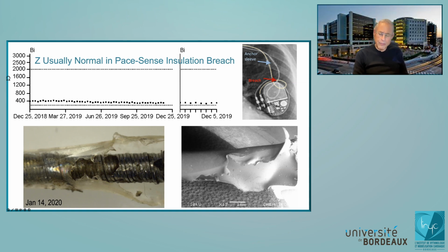So the question now comes, how close does the contact of the lead need to be with the can to measure an abnormal impedance? And how close does it need to be to get an abnormal electrical signal from where you're picking up, say, signals off the pectoral muscle that will enter the pace-sense circuit through that insulation breach, because that's sitting right on the pectoral muscle. So here's what you need to know.